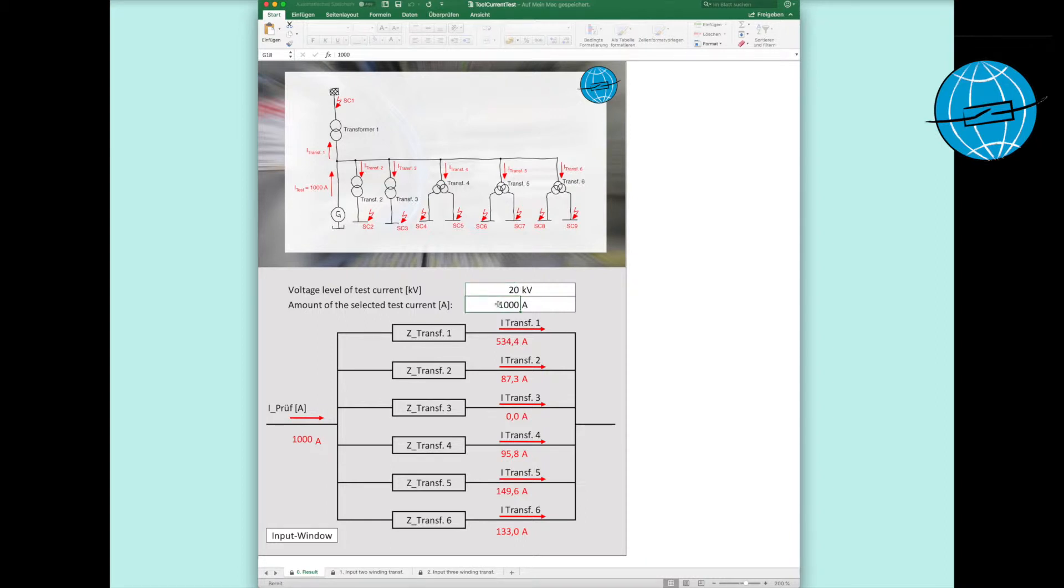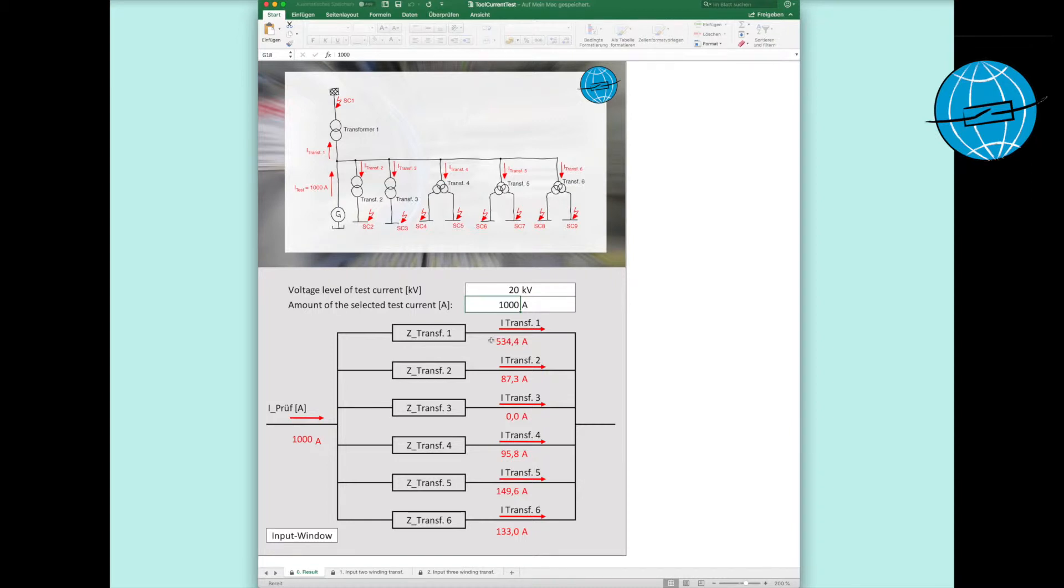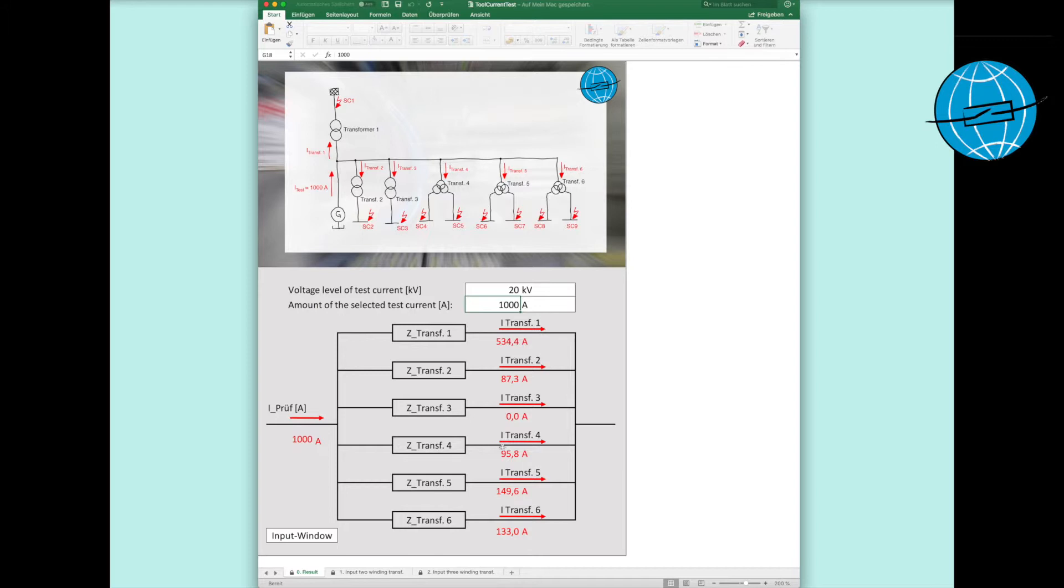In the second cell, we enter our test current and we can read off our results. So, a 20 kV side current of 534 amps would flow via transformer 1. Over transformer 2, a current of 87 amps will flow, and so on.